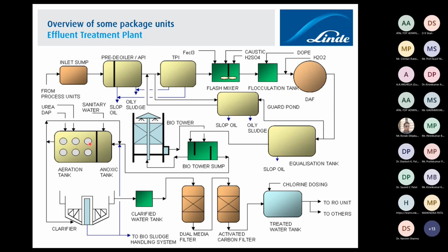That's why we have to send this water back to the clarifier. The clarifier has a slow-moving rake arm. At the bottom, it collects the sludge, and from the top overflow you get the clearer water. Here you will get water with less than 5 ppm impurities, and that water is further stored in a clarified water tank and then sent to the dual media filter.